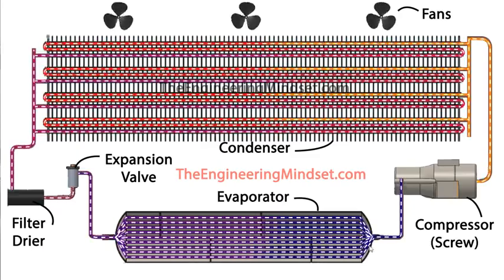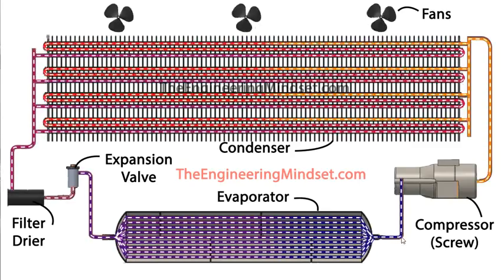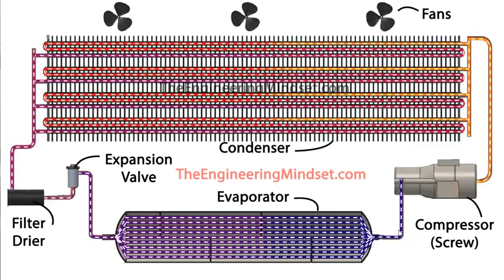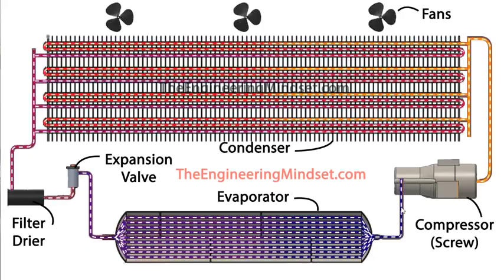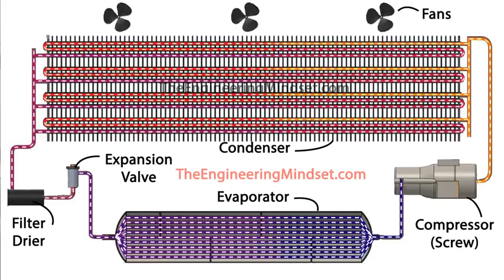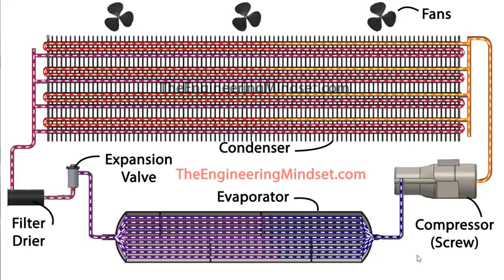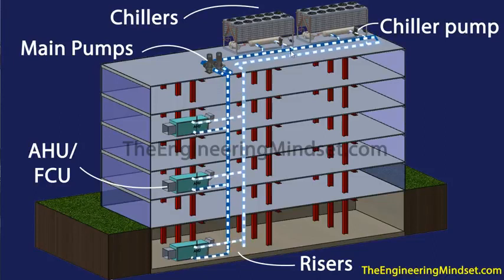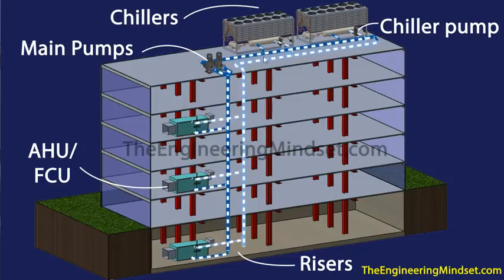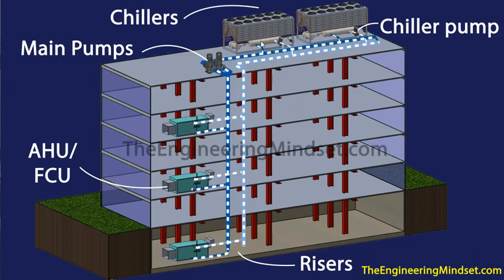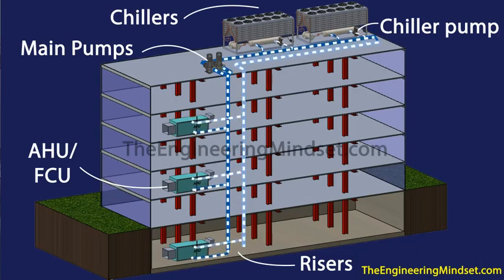So by the time the refrigerant leaves the evaporator, at this point here, it's about to go off into the compressor. That should then be a low pressure, low temperature, saturated vapor. Now if you remember, we had the chilled water flow, and also the return coming into this evaporator, so we'll have a look at that as well.